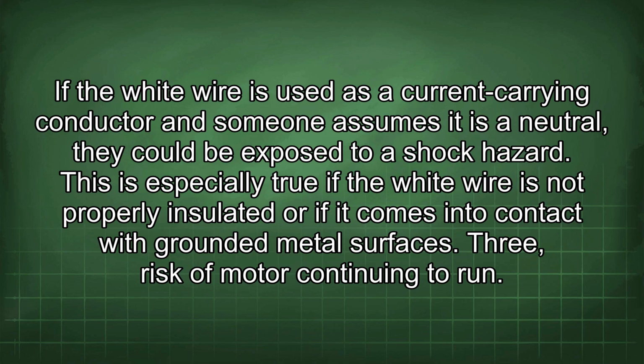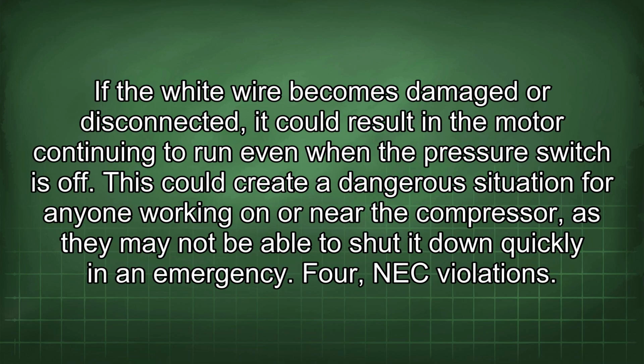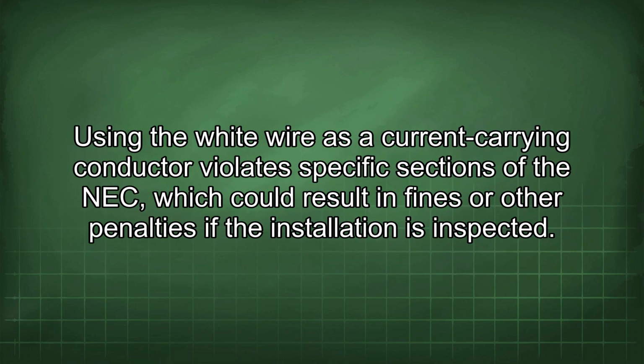This is especially true if the white wire is not properly insulated or if it comes into contact with grounded metal surfaces. 3. Risk of motor continuing to run. If the white wire becomes damaged or disconnected, it could result in the motor continuing to run even when the pressure switch is off. This could create a dangerous situation for anyone working on or near the compressor, as they may not be able to shut it down quickly in an emergency. 4. NEC violations. Using the white wire as a current-carrying conductor violates specific sections of the NEC, which could result in fines or other penalties if the installation is inspected.